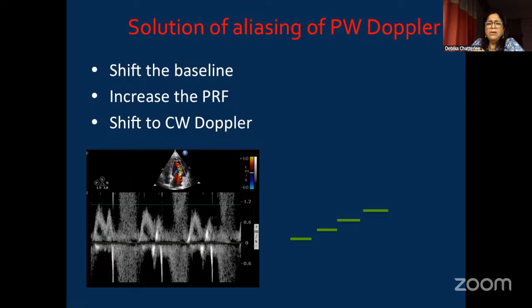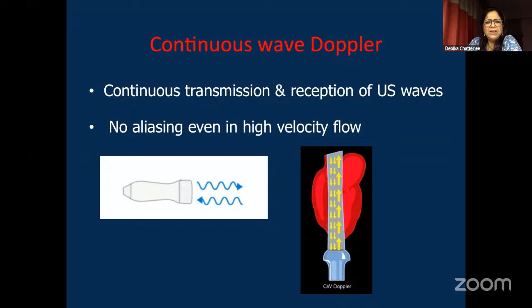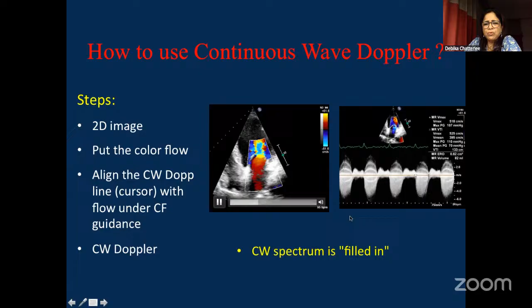Well, what is the difference? See, here the sampling is continuous. There are two crystals. One is sending the signal and another is receiving the signal. So continuous sampling is what is used in continuous wave Doppler, as a result of which there is no aliasing, no Nyquist limit. So you can record a very, very high velocity flow, as in this case of mitral regurgitation, where a very high velocity is also picked up fully by the continuous wave Doppler.